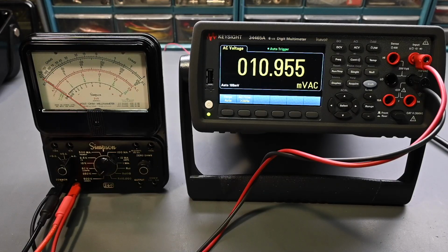And that fan noise that you hear in the background is that Agilent 6812B that's running. The fan's a little bit on the loud side. It's a pretty big cooling fan in that instrument. Now for the 2.5 volts AC, I'm going to use my function generator. It's a BK Precision 4062B, and that provides a very accurate and stable output, and it will work very, very well for the 2.5 volts AC. So I have it on the sine wave output. And the AC source can go down to 2.5 volts, but the function generator is even more accurate. So I'll go ahead and just use that for that low voltage range.